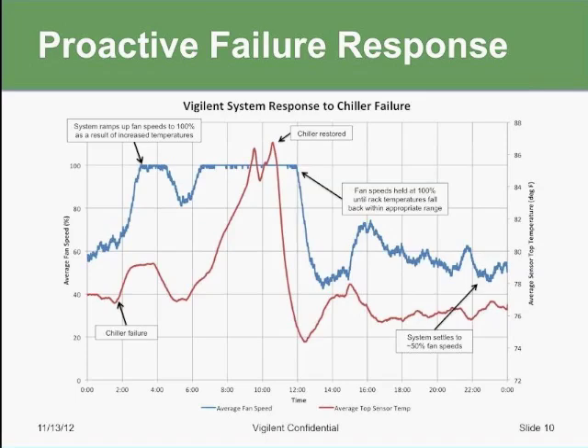Then at about 4 o'clock in the morning, the chillers restored just briefly for a few hours, but then failed, and you can see the temperatures go up to about 86, 87 degrees. And again, the cooling system responded and provided full cooling until noon, when the facility staff had come in the building, and it took them a few hours to restore the chiller. Once temperatures had then dropped back into adequate levels, the Vigilent system dropped fan speeds along with it. And so by the end of the day, the temperatures and fan speeds were back to where they were before this incident had occurred.